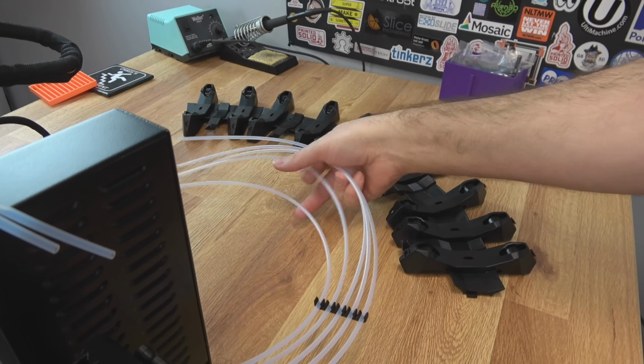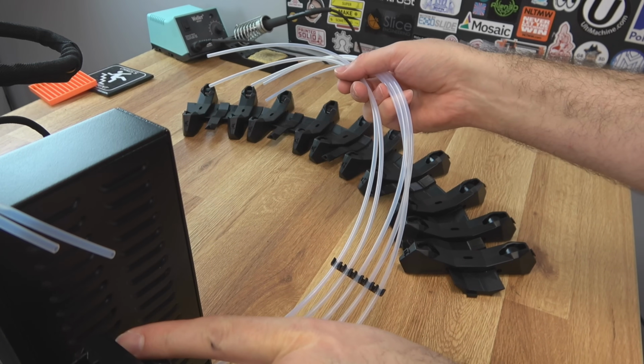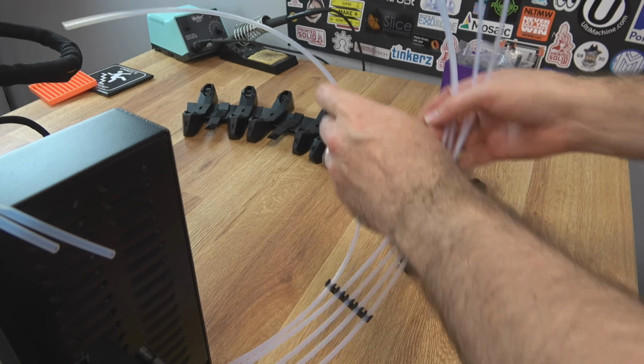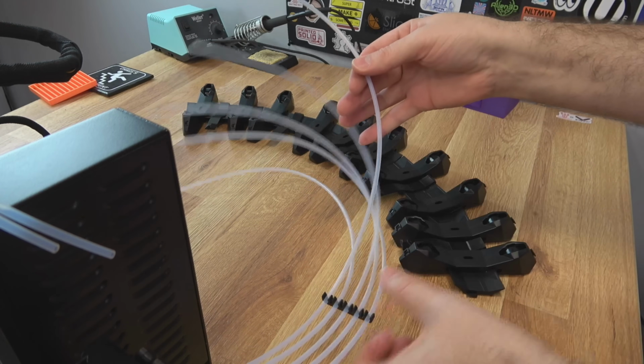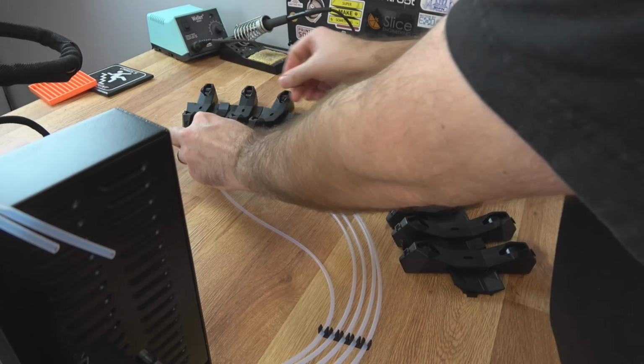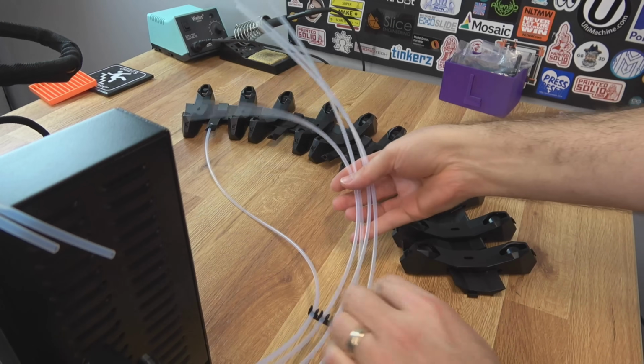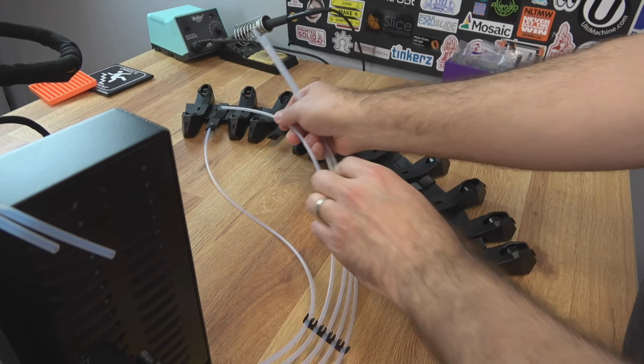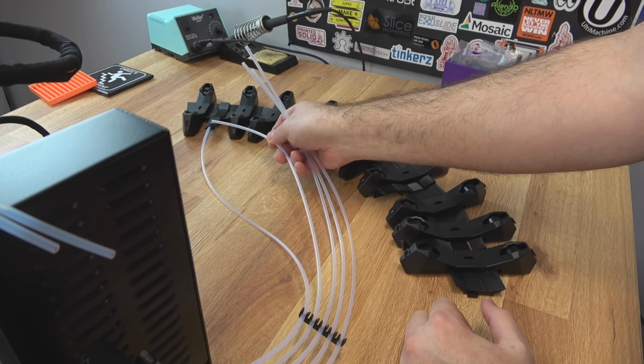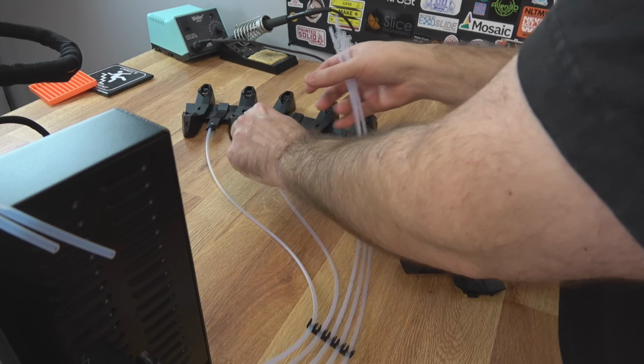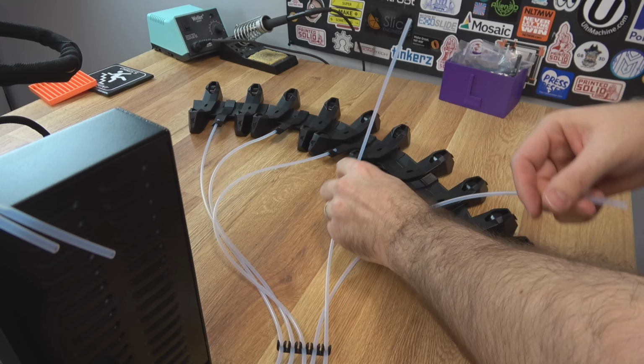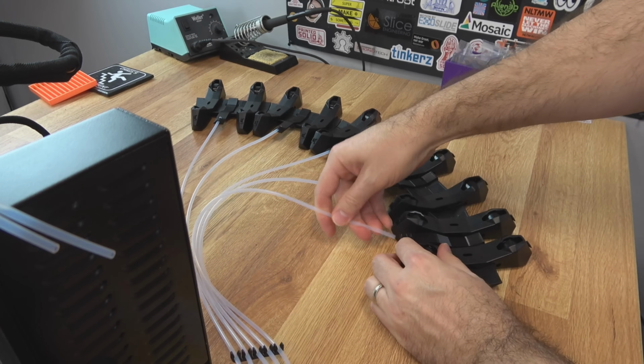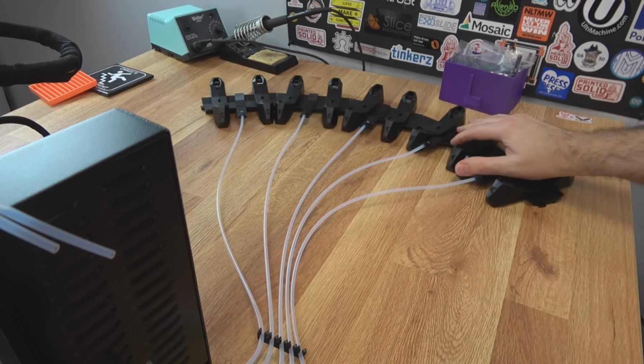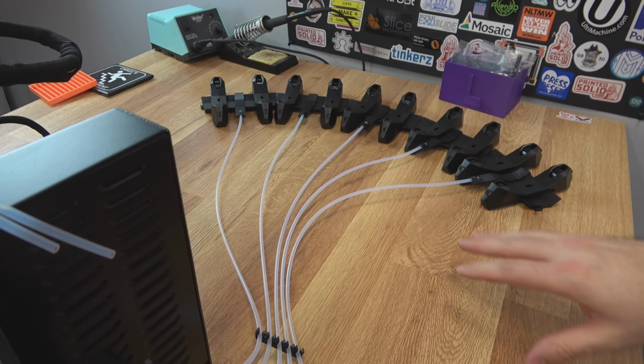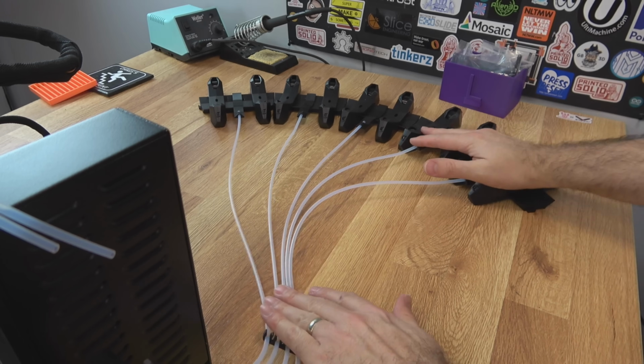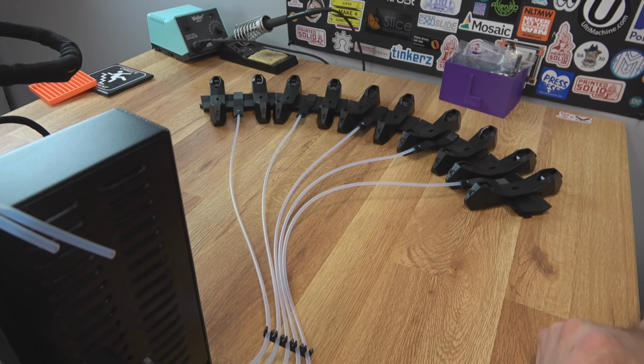And then we have all the tubes that come out of the buffer. They are labeled 1 through 5 as well. But in this order, what I just showed you, this one is the first one. So the furthest one out. We'll just press it into the spool holder. I like to leave about 5 millimeters on the other side. We don't want the tube interfering with the spool as it moves. But then tube 2, tube 3, tube 4, and tube 5. Now you can kind of adjust things now that they're plugged in. You want to keep things as organized as possible to make it not confusing.